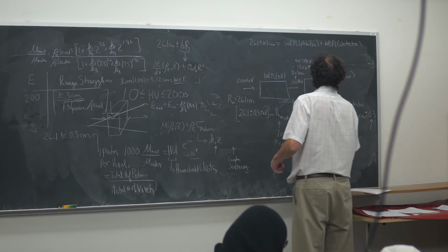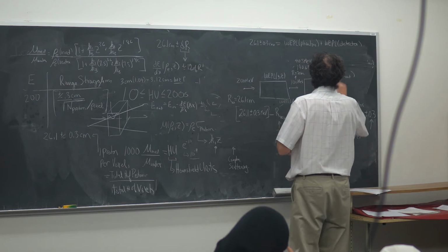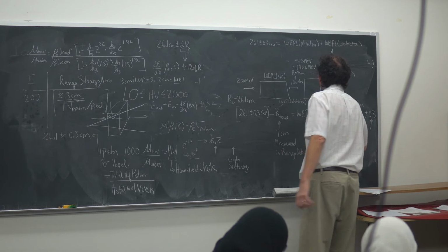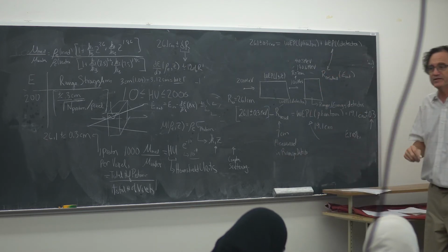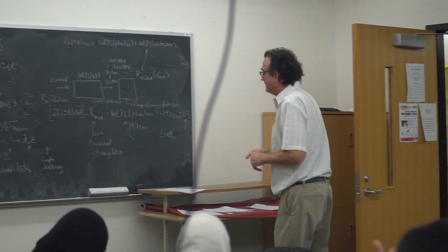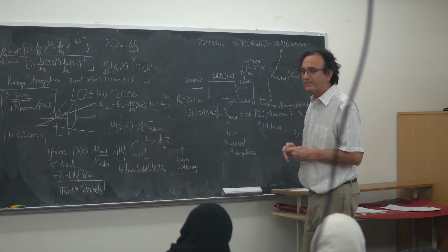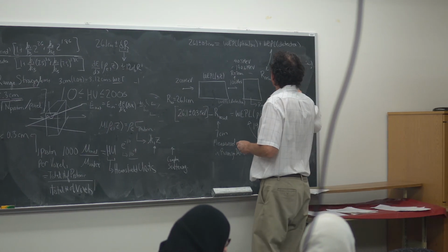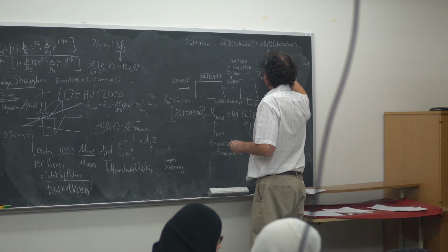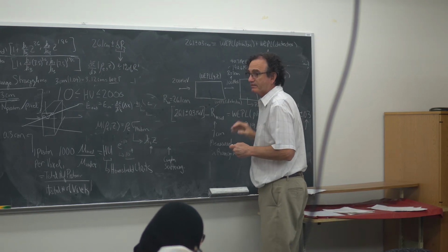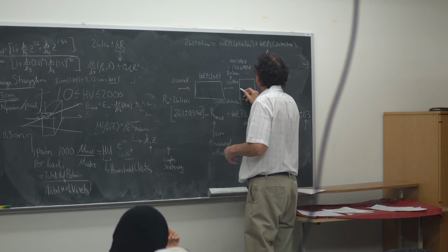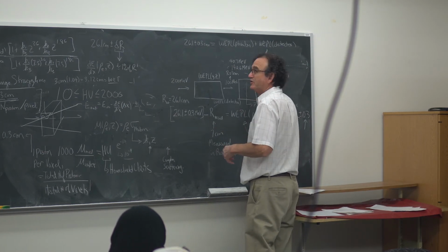And this is the residual range of the detector if the detector is water equivalent. And if it's not, we have to make a correction for it. But oftentimes the detector itself is water equivalent or very close to it. And so we can think of the residual range in the detector as being the water equivalent path length of the proton in the detector until it's stopped, because the proton's going to range out in here, right? The proton's going to go in here until it's stopped.